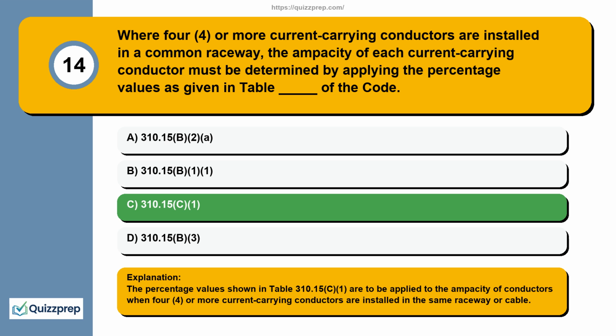The percentage values shown in Table 310.15(C)(1) are to be applied to the ampacity of conductors when four or more current carrying conductors are installed in the same raceway or cable.